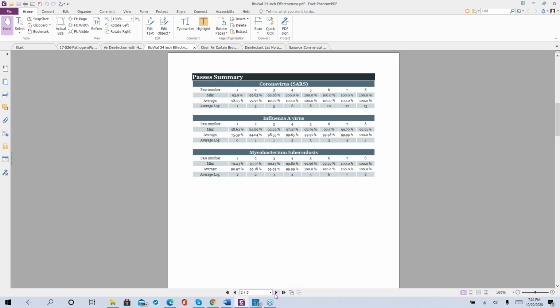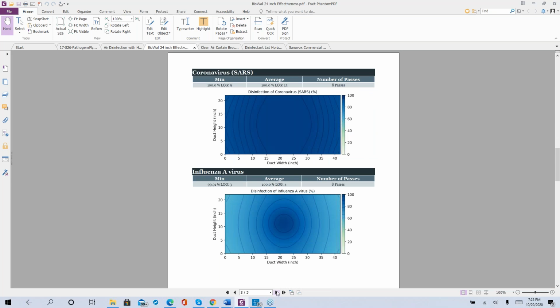So that's a little bit more of a custom kind of solution there, Paul? It is. And so then they'll also, if you're indicating that you're very worried about corona or influenza or tuberculosis, they will put whatever the pathogen, allergen, VOC, or whatever it is, and tell you what your minimum and average is and how many passes it will take for you to reach that. So as you can see with tuberculosis, you need at least 3 passes to properly kill it in order to get up to that 99%.